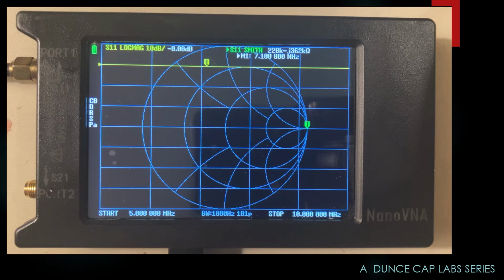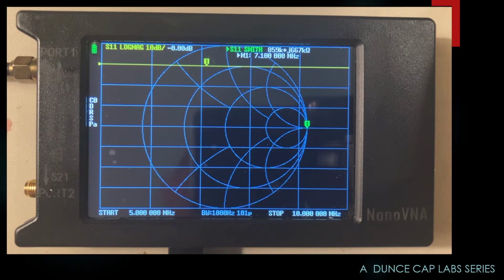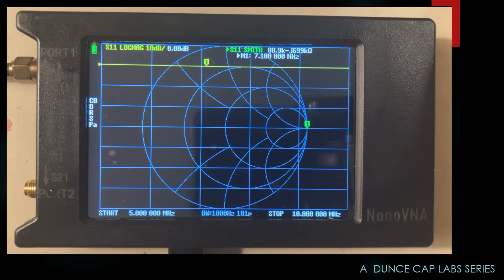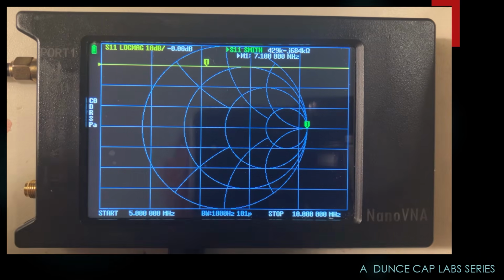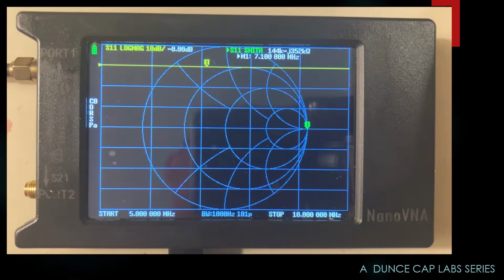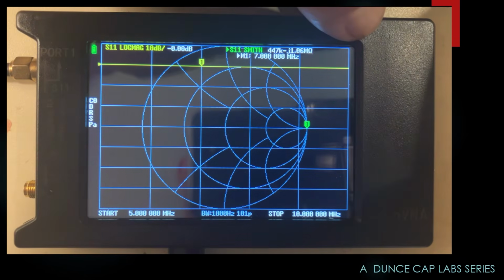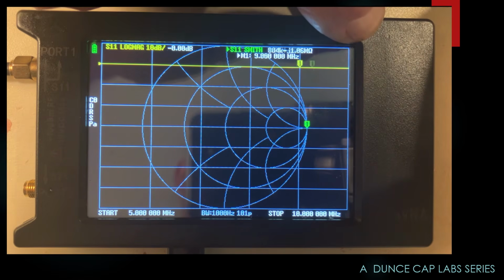And I even have a video for that. Anytime you want to check calibration, it's easy. Let's say I've got my little cable still on here, but there's no termination, it's not hooked to anything. I should see this cursor right here, and if I vary my frequency, it shouldn't move — and it doesn't.